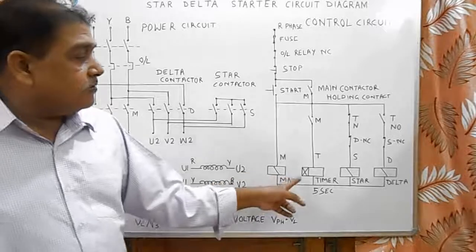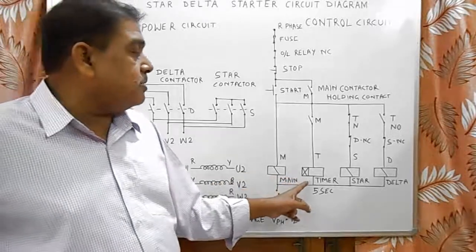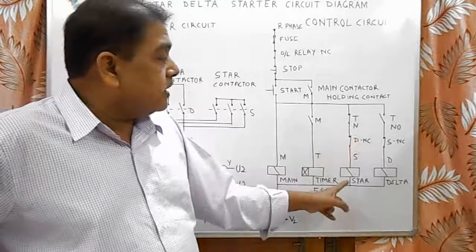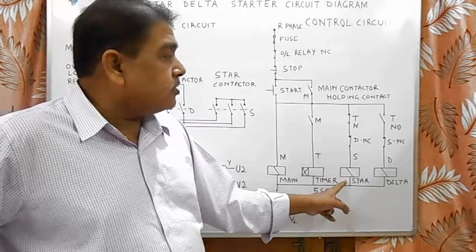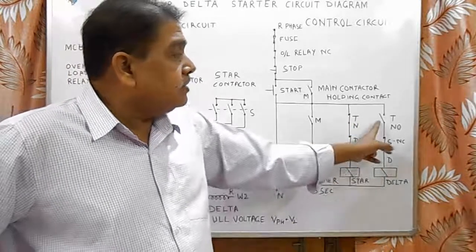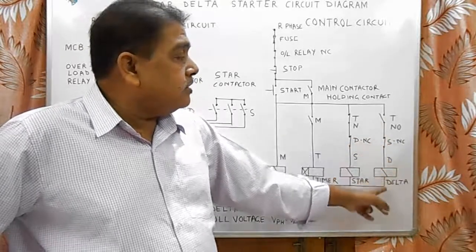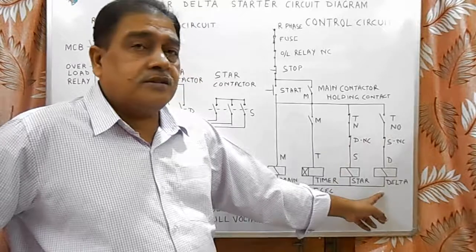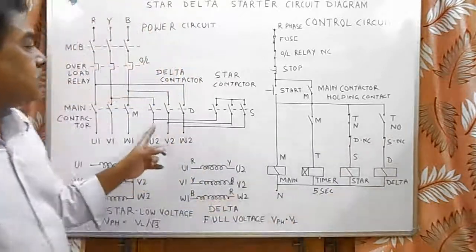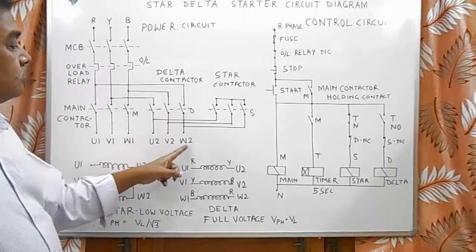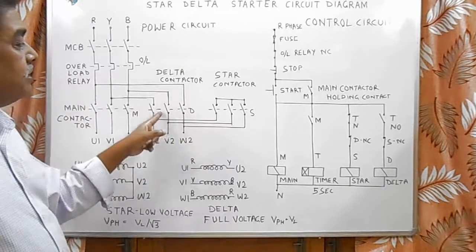After 5 seconds completion of the timer, the NC contactor opens up and star contactor drops out, whereas the NO contactor of the timer closes and delta contactor starts. As soon as delta contactor starts, supply goes to U2, V2, W2 with the help of delta contactor.